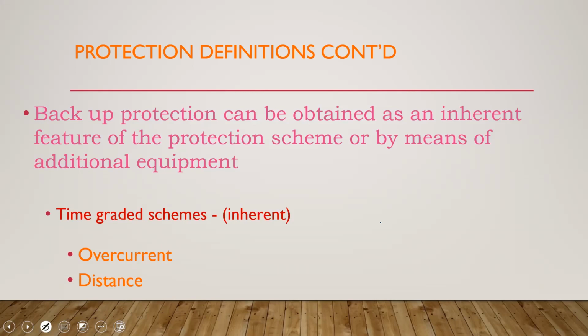And remember, students, we are dealing with protection fundamentals, so I'm not getting into the details. If you want the details, see you in January, right? So your time-graded schemes, your overcurrent and your distance schemes, have backup as an inherent part of their operation.